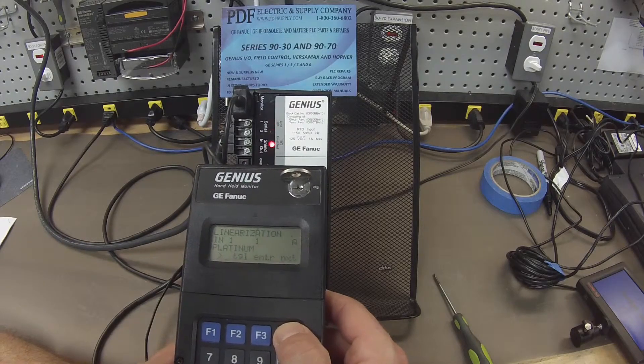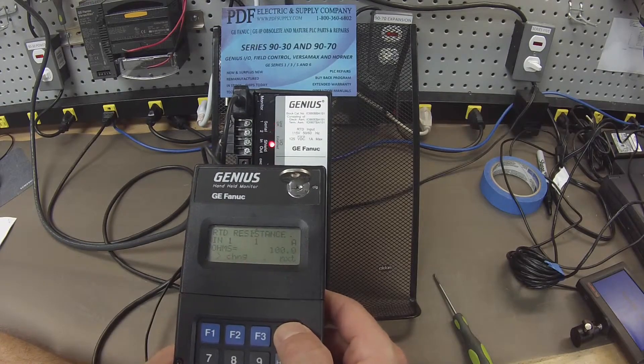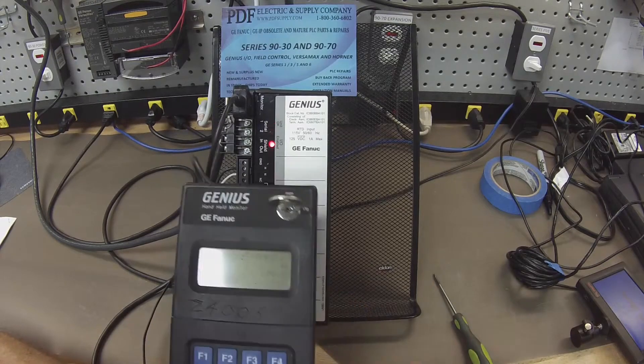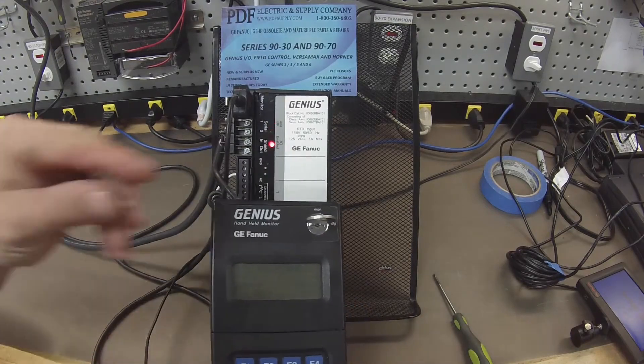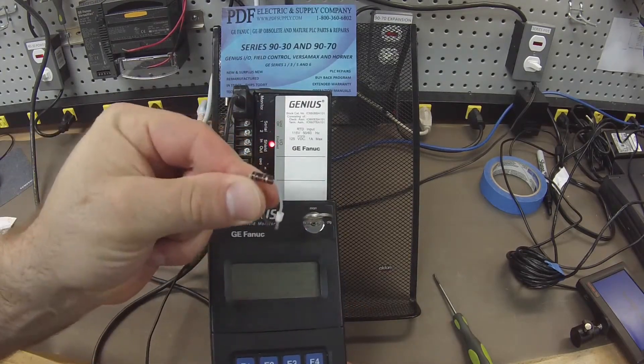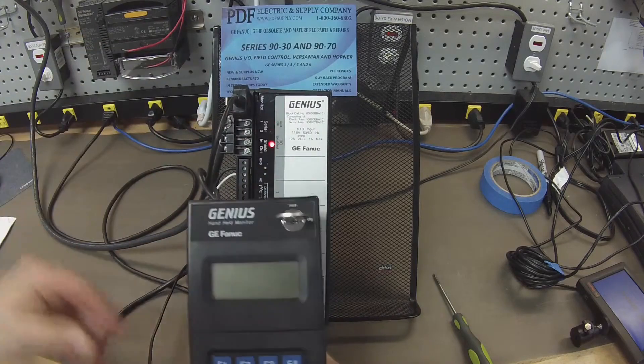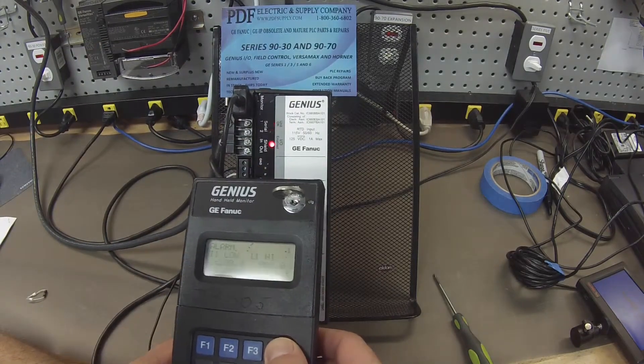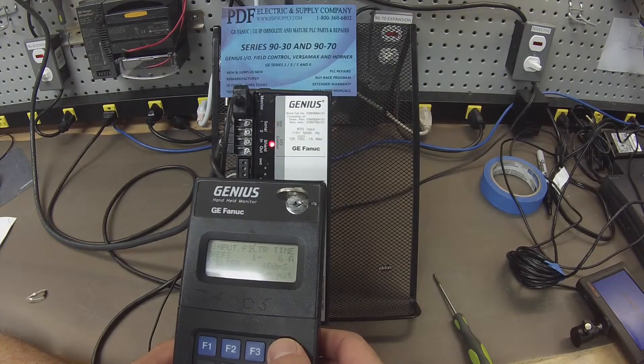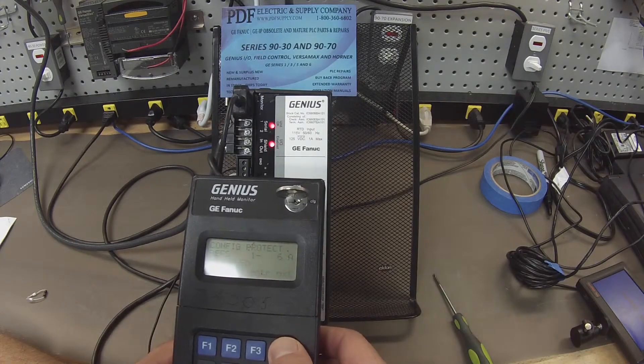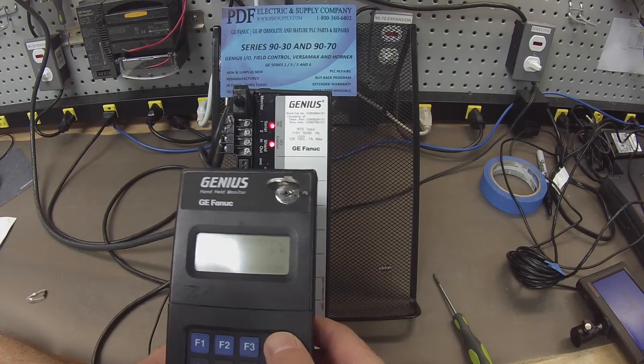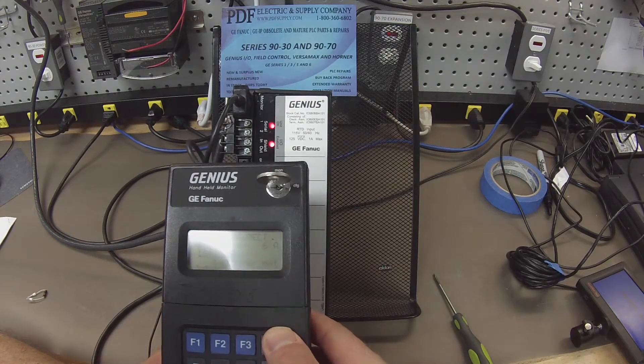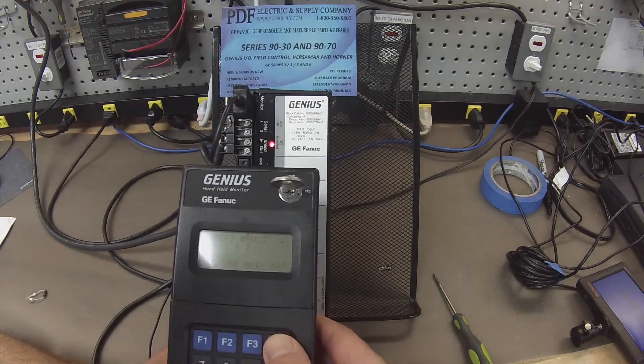Celsius, platinum linearization, 100 ohms. That's the resistor that I'm using is actually a 100 ohm resistor. This is just to test each channel. So that's OK. 400 millisecond input filter time. Configuration protection is disabled. If yours is enabled, you have your configuration protect on. I would leave it on.